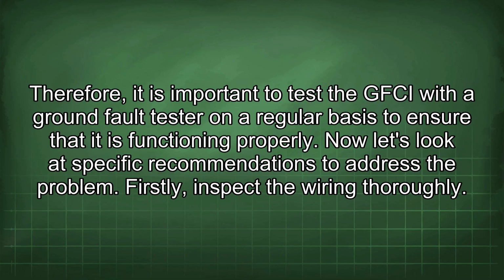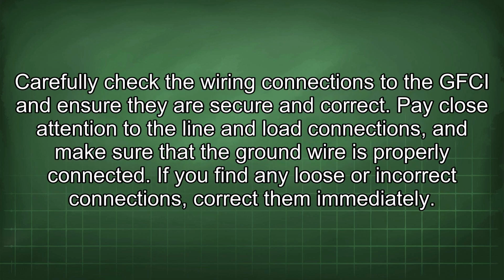Now let's look at specific recommendations to address the problem. Firstly, inspect the wiring thoroughly. Carefully check the wiring connections to the GFCI and ensure they are secure and correct. Pay close attention to the line and load connections and make sure that the ground wire is properly connected. If you find any loose or incorrect connections, correct them immediately.